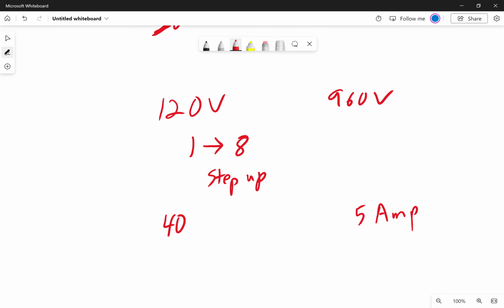I could also ask what the volt amps on the secondary side would be. To find that, I just take my 40 amps on the primary side times the 120 volts on the primary side, which gives 4,800 volt amps, and that's good on both sides.